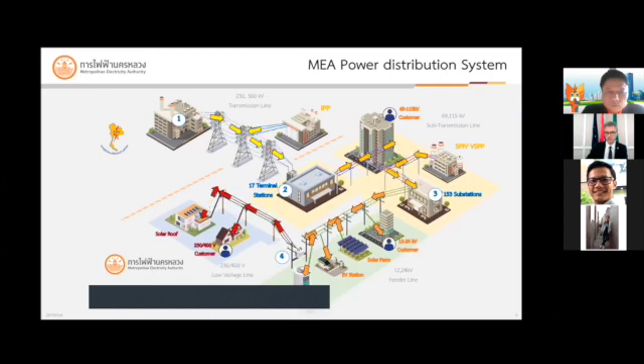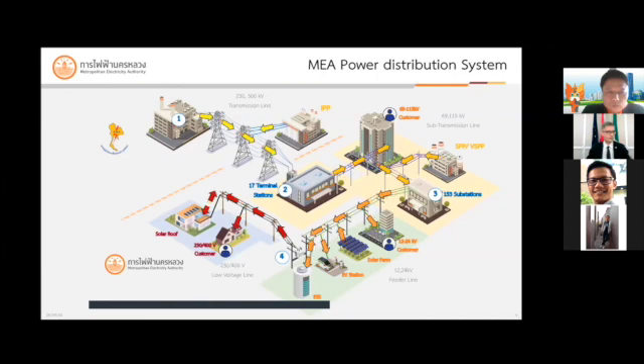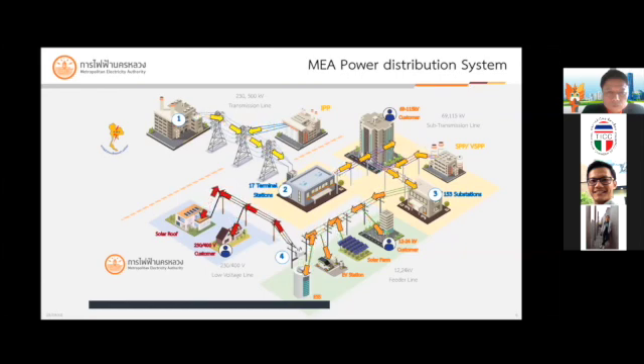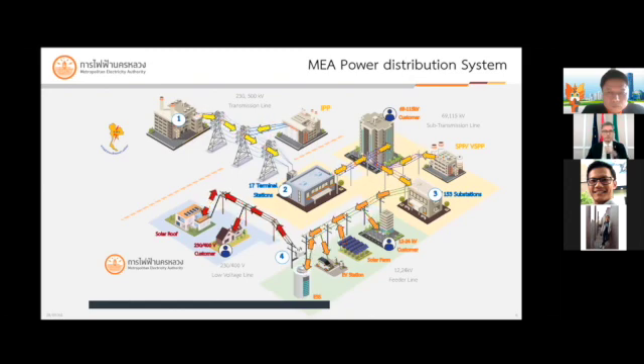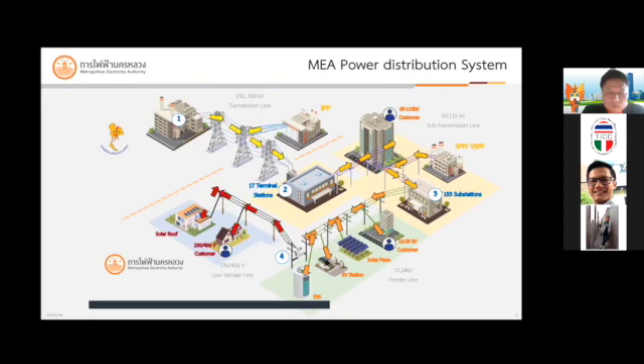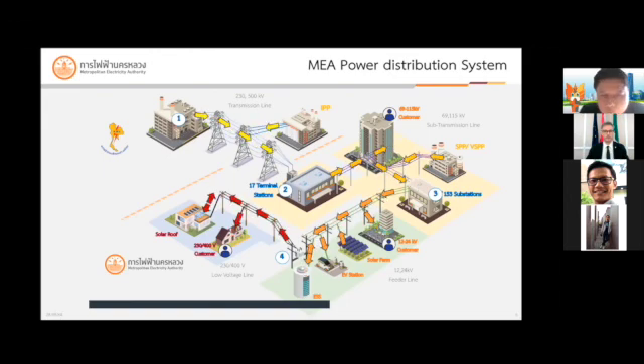Then, the terminal station will step down the voltage to 69 or 115 kV and transmit power to 69 and 115 kV customers, and substations showing number 3 in the picture. SPP or VSPP connecting to the grid at this voltage level can feed the power to the system. The substations will then step down the voltage and transmit power through feeder lines to 12 and 24 kV customers and distribution transformer or number 4 shown in the picture.